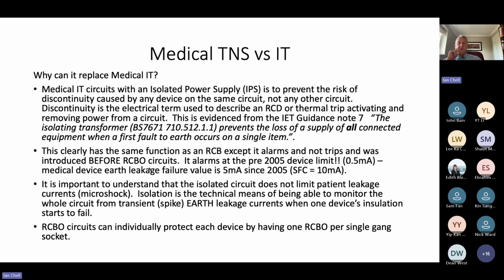IPSs alarm at the pre-2005 device limit, half an mA. And now medical devices are only failed if the leakage value is above 5 mA in normal condition, or 10 mA with a single fault on. So you've got to understand that the isolated circuit does not limit patient leakage, because that's in microamps, okay? It's not in the milliamp range. So how is an isolated power supply protecting the patient? Yes, it does provide some form of current limiting, but it doesn't tally with anything now.